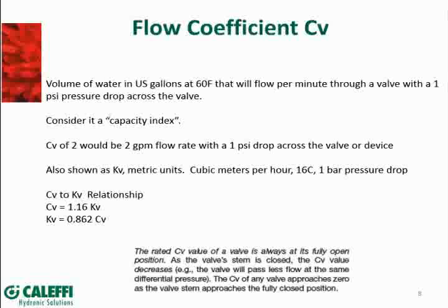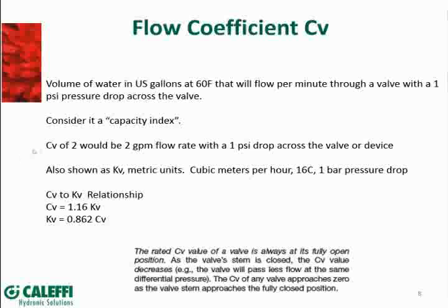I saw one analogy that considered it to be a capacity index. There are a lot of different ways that people interpret and explain this. To me that made the most amount of sense, and I think the formulas will kind of substantiate that definition. For an example, a CV of two would mean a two-gallon-per-minute flow through a valve or device would have a one PSI pressure drop across that device.